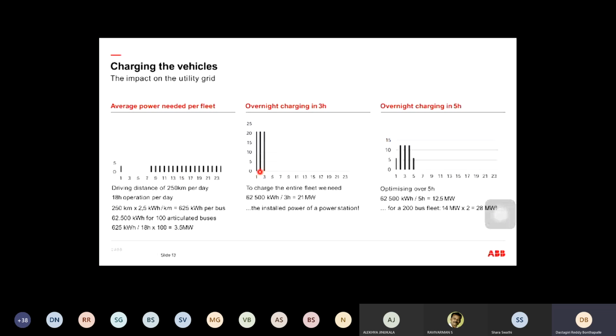If it's an existing city, building this depot charging station with 21 megawatt is difficult because you need extra land, you need to lay power lines, and then there's power utility charges. You install 21 megawatt but use it for only 3 hours a day, so you pay additional charges for that. Even if you stretch it to 5 hours instead of 3, you still need 12.5 megawatt of power available at your depot.